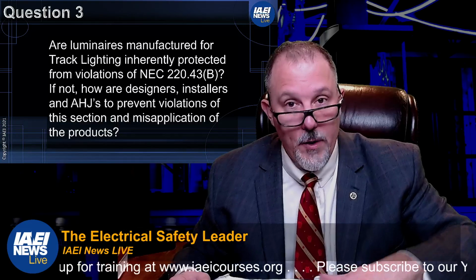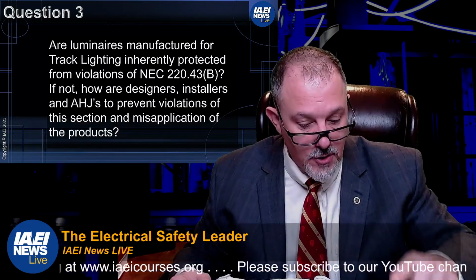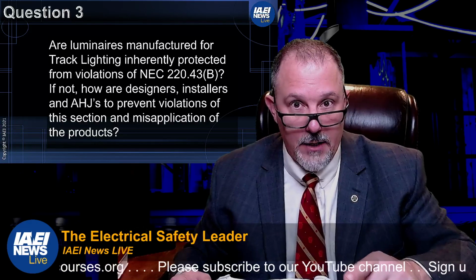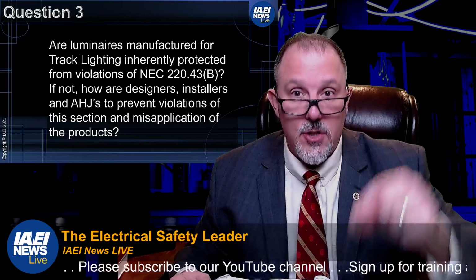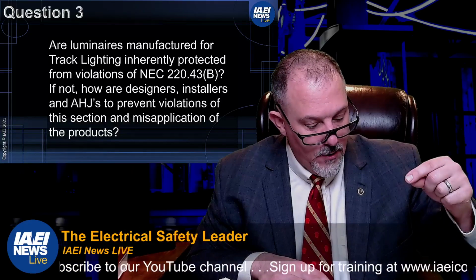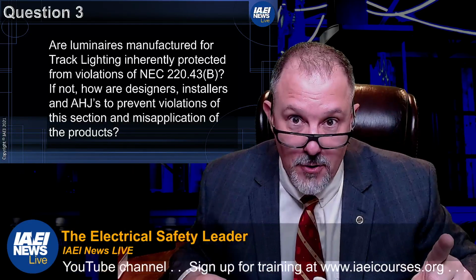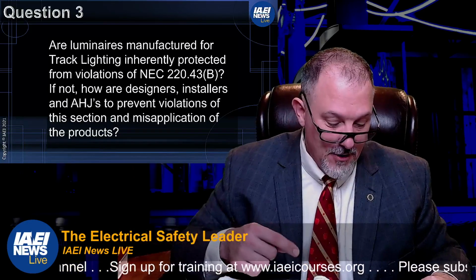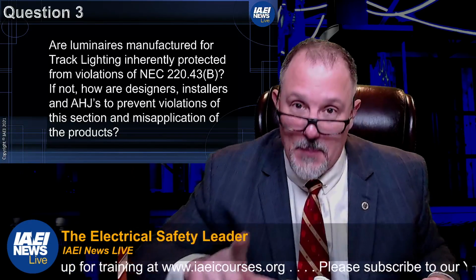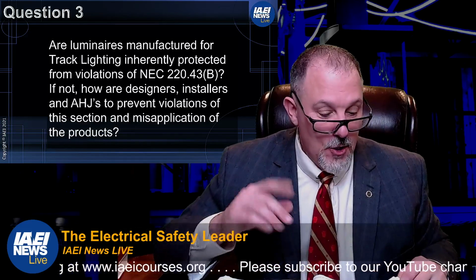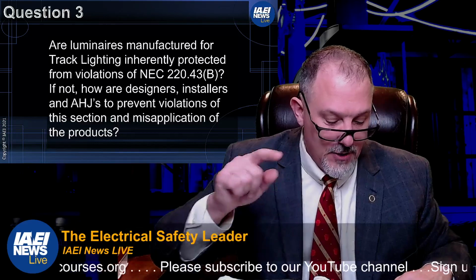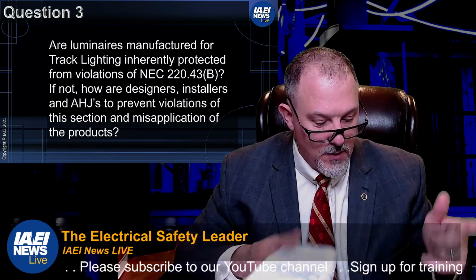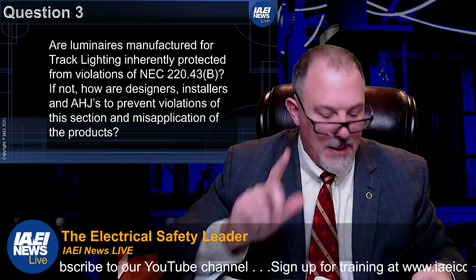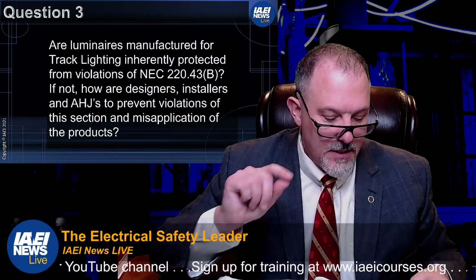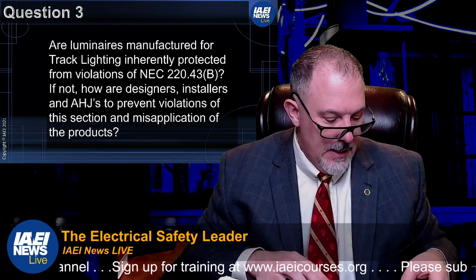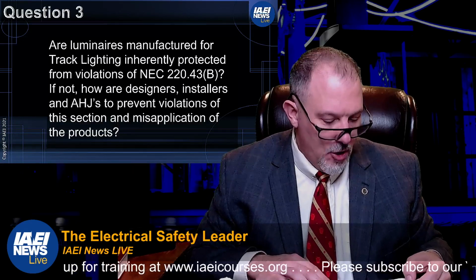So we know we are in Part 2 of Article 220, which deals with branch circuit load calculations. And we are not in Part 2. We're in Part 3, feeder and service load calculations. So we're not in Part 2. I went too far up. So we're in Part 3, feeder and service load calculations. Part 1 is general. Part 2 is branch circuit load calculations. Part 3, which begins with 220.40, is feeder and service load calculations. And 220.43 is show window and track lighting.